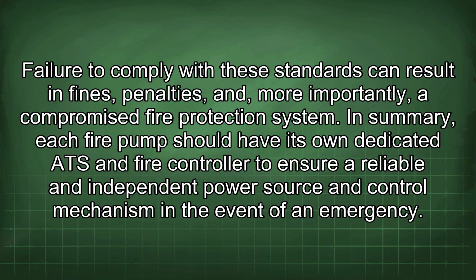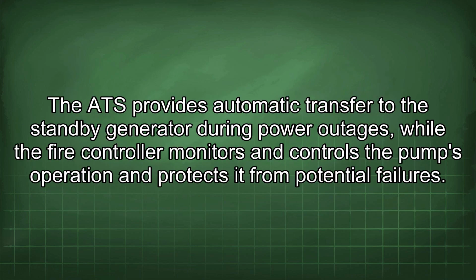In summary, each fire pump should have its own dedicated ATS and fire controller to ensure a reliable and independent power source and control mechanism in the event of an emergency. The ATS provides automatic transfer to the standby generator during power outages, while the fire controller monitors and controls the pump's operation and protects it from potential failures.